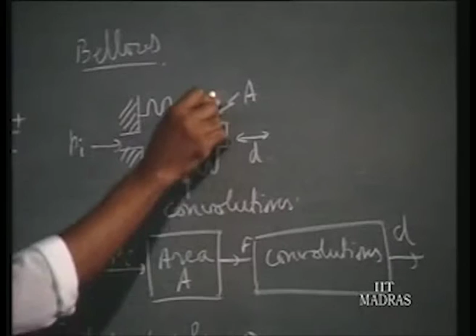Next one is bellows, another elastic element. Here you have more deformation than even a corrugated diaphragm. That is the advantage, because we have so many convolutions and we allow the pressure here. The pressure acts over this area, the end pressure, and as I told, the end of the bellows should be closed with a plug. So the whole area converts the pressure into a force. Pressure times area gives force, and that force acts on the spring material convolutions, which give way. So by using convolutions, the force F is converted into a displacement D.